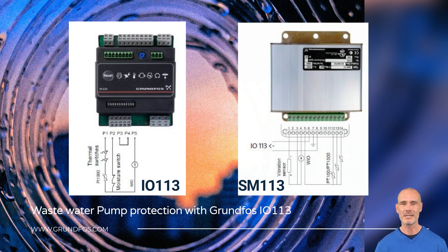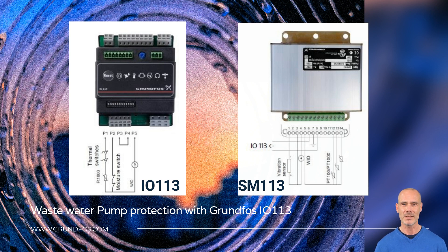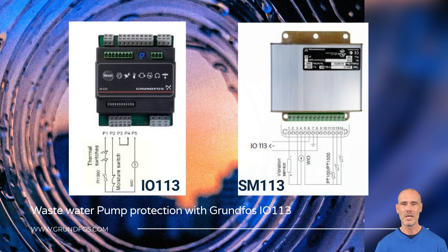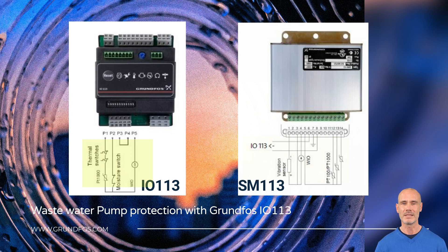With the SM-113, the system will collect sensor data from vibration sensors and water-in-oil, both analog signals, additional bearing temperature sensors PT-100 or PT-1000, and the stator temperature.